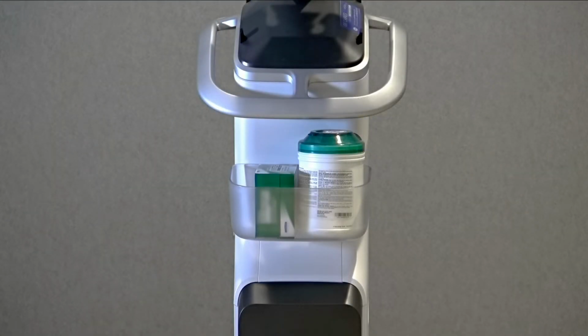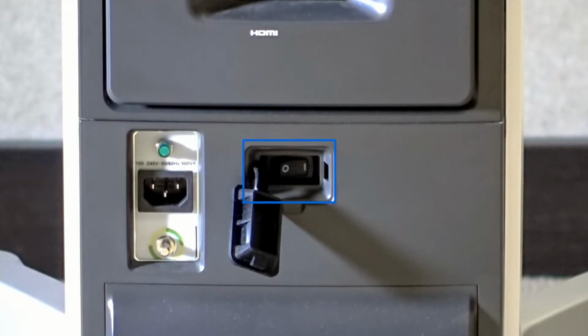The venue system comes with an onboard storage bin. Additional optional accessories include an ECG module, a black and white printer, and a barcode reader. When transporting your system, always turn off the circuit breaker to save the life of the battery.